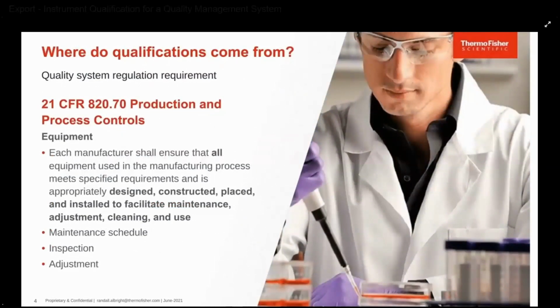As we have mentioned, qualifications are an industry standard accepted in response to regulations. What would be an example of such regulations? Directly applicable to Thermo Fisher Scientific customer and our instrumentation is quality system requirements of productions and process controls and process validation. If we dig deep into 820.70G, it defines the essentials of what equipment performance needs to be documented. We have highlighted the pertinent language that guidance interprets for the industry. Again, it's not calling out the IQ, OQ, PQ mechanism, but rather what needs to be documented.